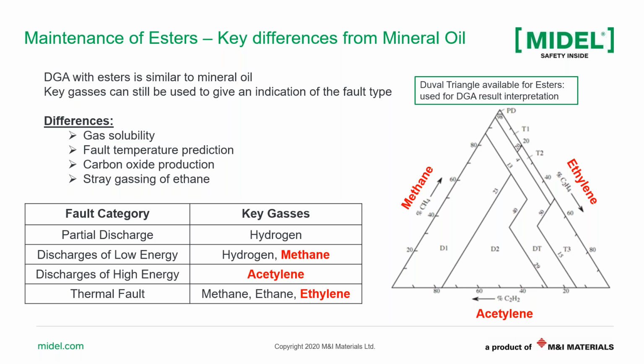Also, the amount of gases produced can indicate different fault levels. In esters, we have carbon oxide production because of that ester linkage. And also sometimes in natural esters, you have stray gassing initially after the heat run test, because they have unsaturated bonds which oxidize with dissolved oxygen. So you can produce ethane. Now these are the key differences, but still we have a lot of similarities.